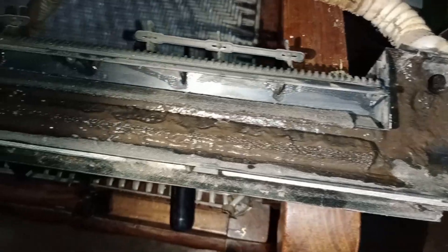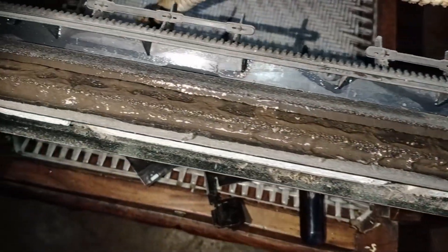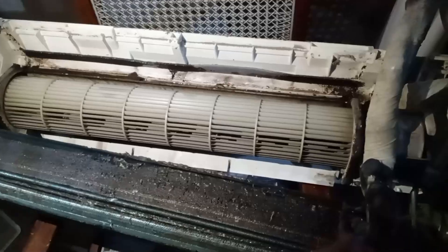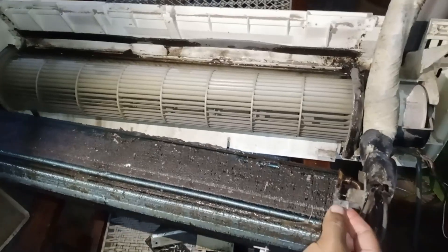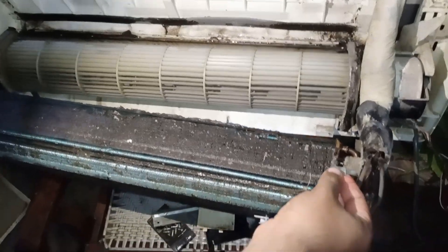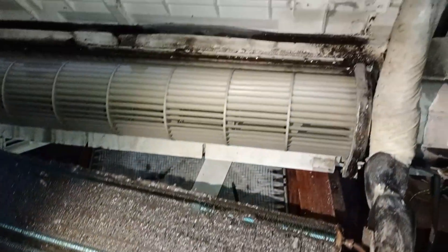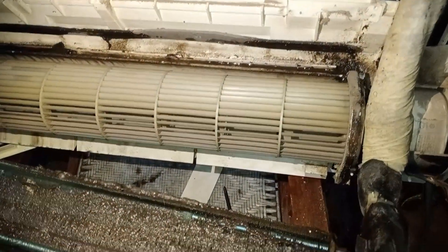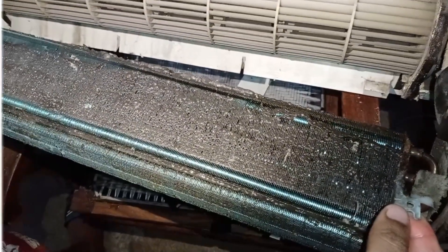The water collector was full of debris, and when the evaporator was removed, its backside was completely clogged with dust. This severe accumulation of dirt is a clear indication of inadequate or improper cleaning previously.